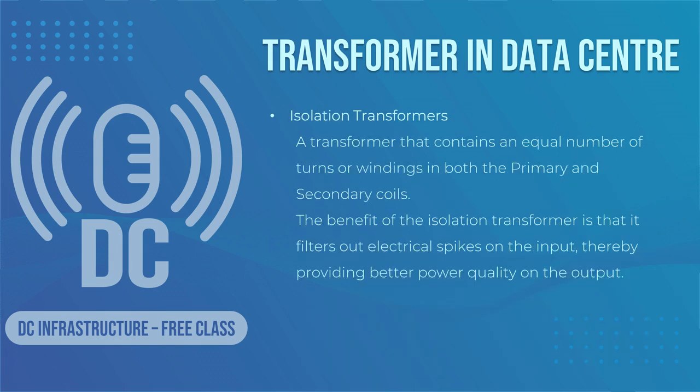An isolation transformer contains an equal number of turns or windings in both the primary and secondary coils. This means the voltage coming into the transformer is equal to the voltage coming out of the transformer. This transformer is usually found in the PDU panel. Within the transformer, the law of induction dictates that transformation takes place without any electrical connection between the input and output. The benefit of the isolation transformer is that it filters out electrical spikes on the input, thereby providing better power quality on the output.